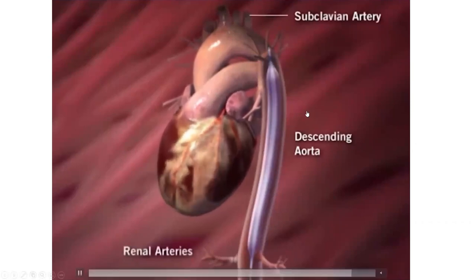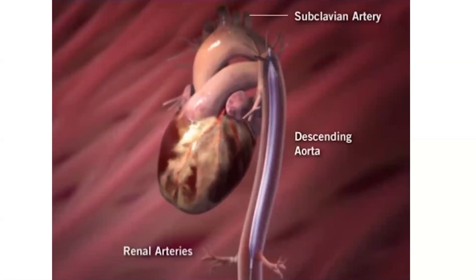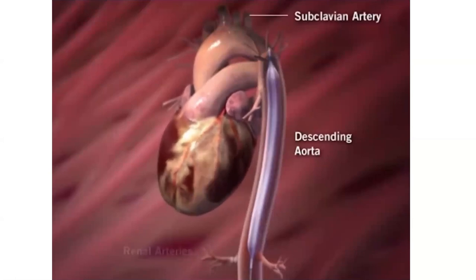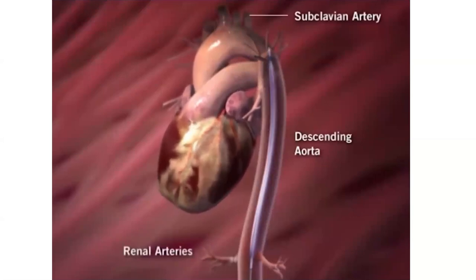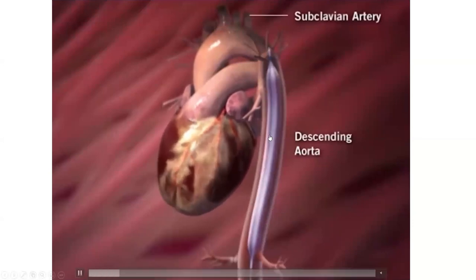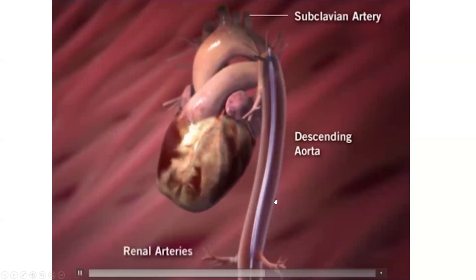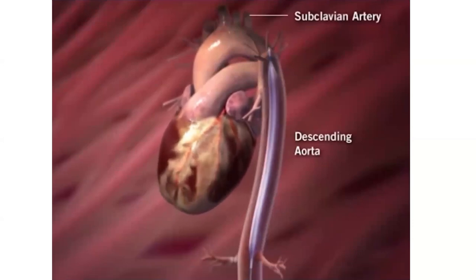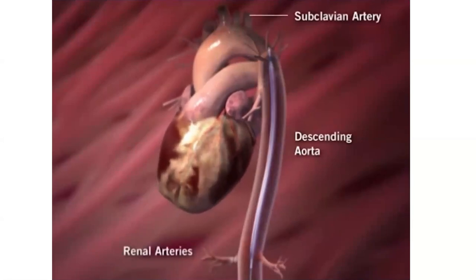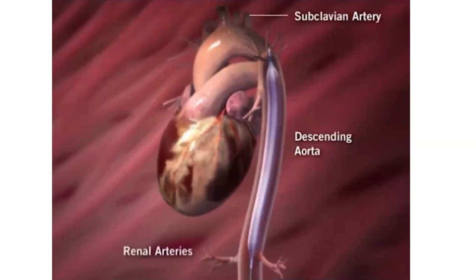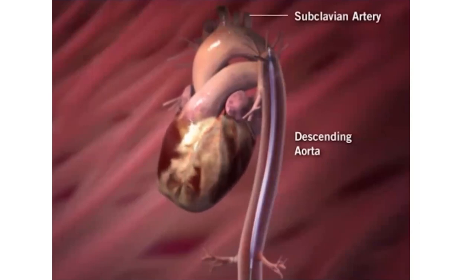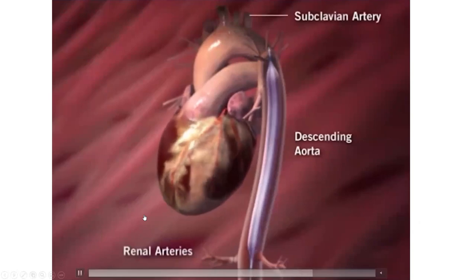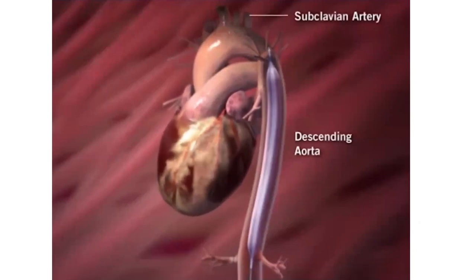Also, inflation in diastole will improve coronary flow, which mostly occurs in diastole for the left heart. 85% of coronary flow to the left heart occurs in diastole. Now, inflation can be done every cardiac cycle, the so-called one-to-one, as you can see in this image, one-to-one mode. But it can also be done every second or third cycle, the so-called 1-to-2 or 1-to-3 modes. The 1-to-2 and 1-to-3 modes are not very supportive and should not be used routinely. They are only valuable for weaning and for adjustment of inflation timing.